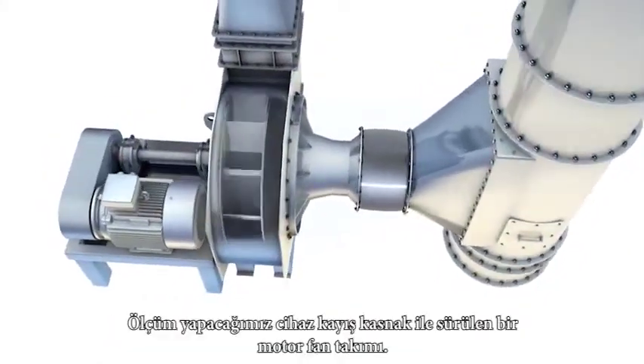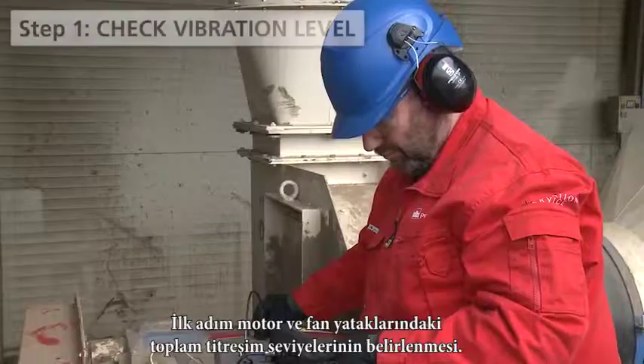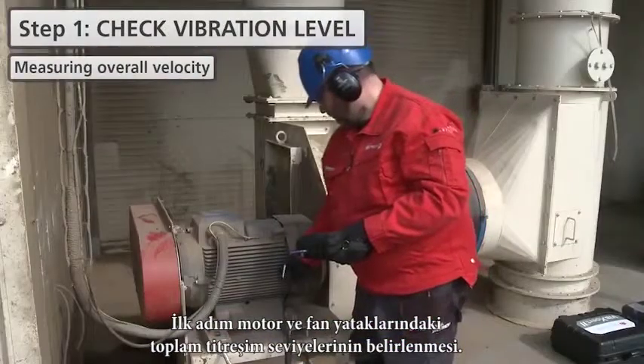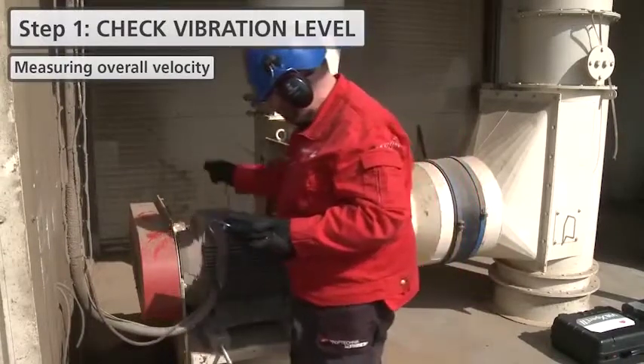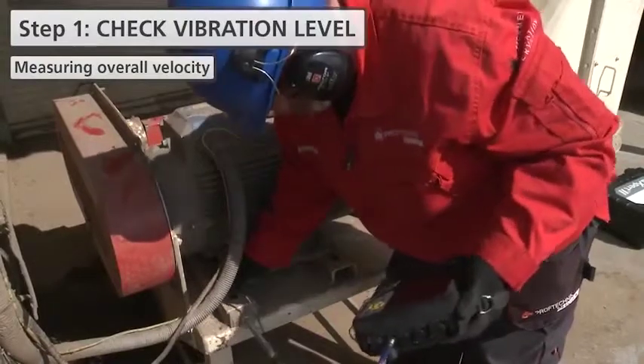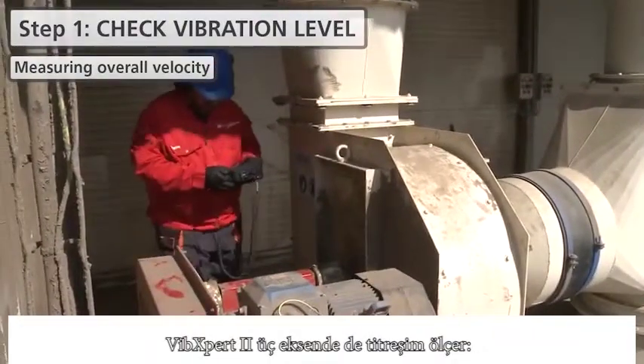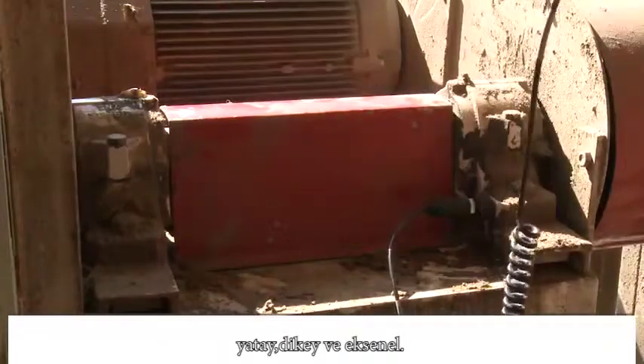A belt driven motor fan set is the object of our measurement. The first step is the verification of overall vibration levels on the motor and fan bearings. VibXpert II measures the vibration in all three axes: horizontal, vertical and axial.